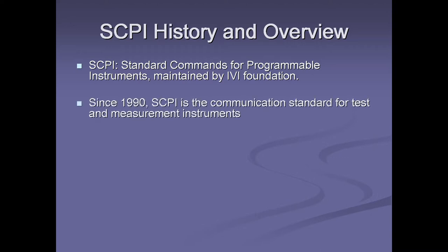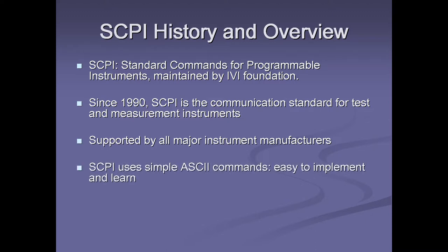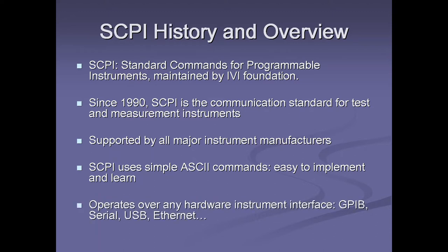Since 1990, SCPI is the communication standard for test and measurement instruments. It's supported by all the major manufacturers of instruments. It uses a simple ASCII command set that's fairly easy to implement and learn. And it operates over any hardware interface: GPIB, serial, USB, Ethernet.